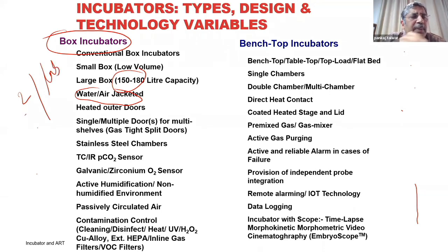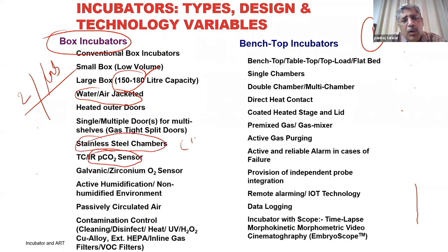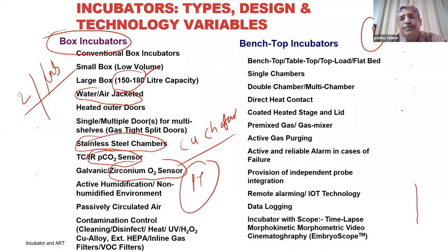When you want to start a lab, and say you want to do around 20 cases a month, buy 2 of them and buy 1 benchtop incubator. These 2 lab incubators should be approximately 150 liters. And you should always prefer to have an IR sensor and stainless steel chambers. Now we are getting copper chambers, which are much better. But these are the ones where we use zirconium oxygen sensors. We use temperature sensors which are platinum. I've told you, PT, platinum.